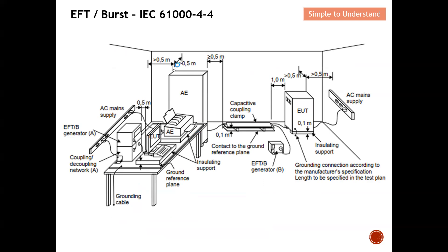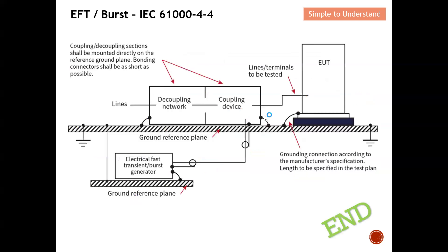According to IEC 61000-4-4, there are two types of tests. One performs the testing through the CDN, and the other performs testing through a capacitive coupling clamp. Most of the time we try to comply under CDN-type testing. If not, we use the capacitive coupling clamp, which couples the noise source onto the conductors of the wire to reach the DUT, and we check whether the DUT still functions.